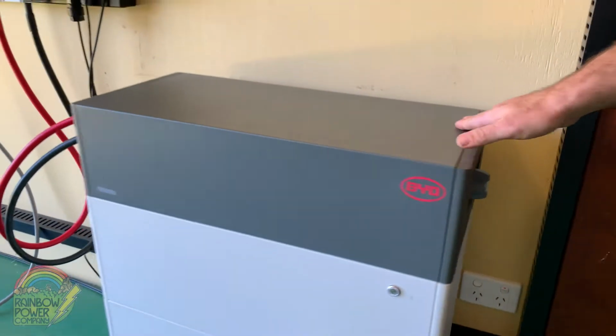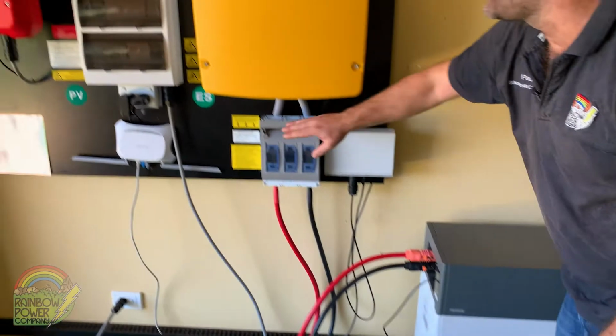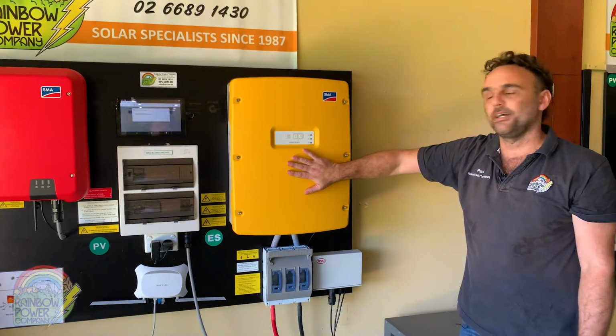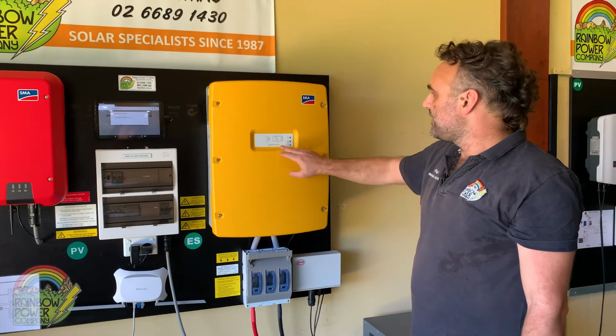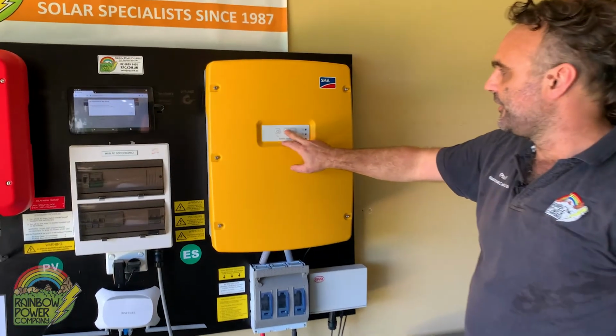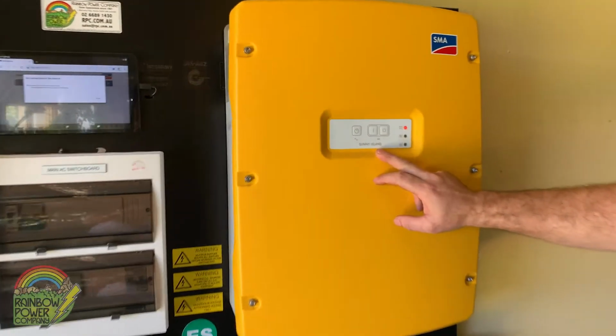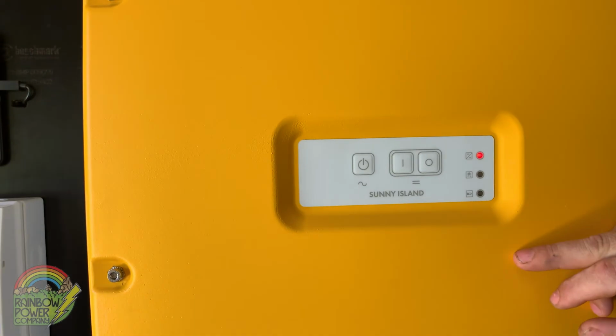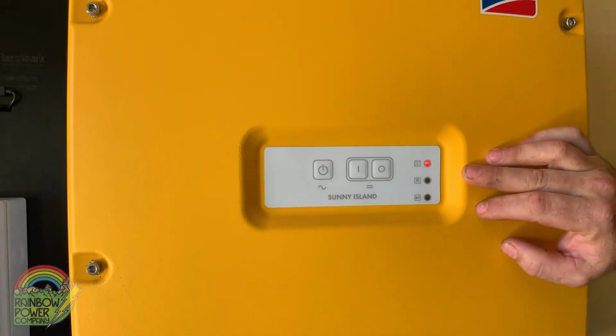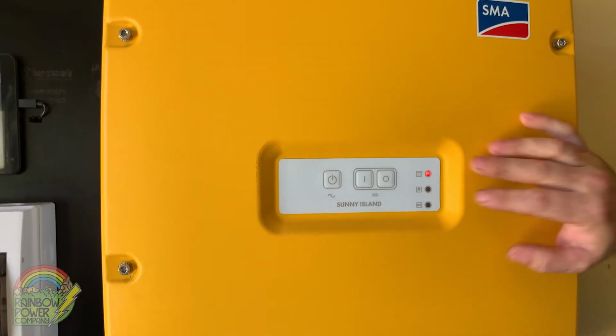We now have power flowing out of the battery, up through the HRC, up to our Sunny Island inverter. To turn the Sunny Island on, we hold our finger on the on button and press it once - it goes through a startup sequence. This can take a few seconds, and it's finished once the lights go green.